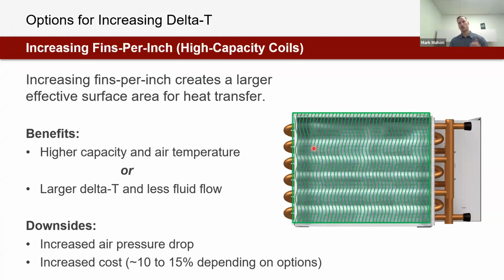Now, this is a well-utilized, well-leveraged product option and market. We have standard coils, which are 10 fins per inch, and all commodity manufacturers have a high capacity coil, which is 12 fins per inch. This essentially just makes a larger effective surface area for heat transfer. For anyone who's familiar with the log mean temperature differential capacity equation, we're increasing our UA. So how much material and how much heat transfer surface do we actually have?